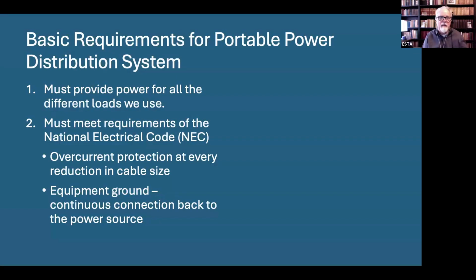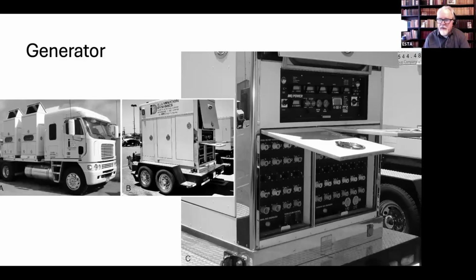So the basic requirements for a portable power distribution system are to accommodate all those kinds of loads, every one of them, and meet the requirements of the NEC. There are a lot of requirements in the NEC, but the two that are relevant to portable power distribution systems are overcurrent protection wherever there's a reduction in wire size, and equipment grounding, continuous equipment grounding from the power source all the way to the load. So those two things are the main things accomplished by a portable power distribution system.